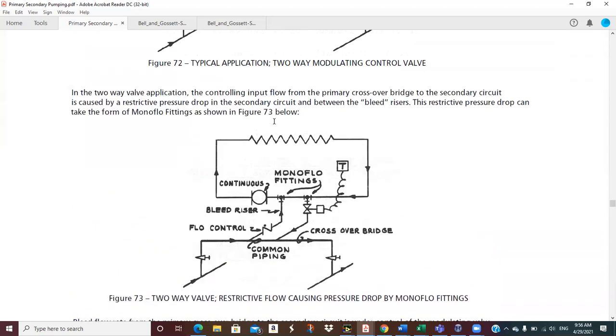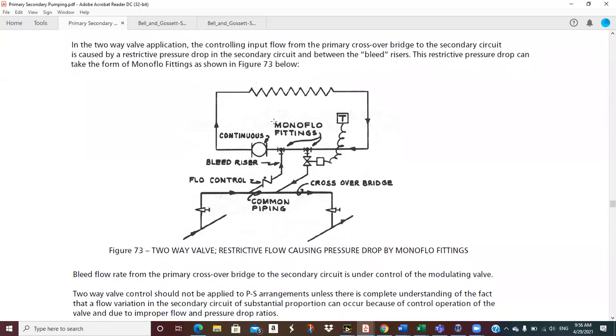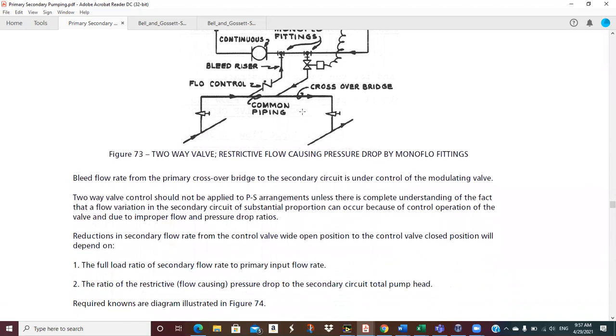Okay, that's a mouthful. But what that's saying is if you don't get the flow ratios and the pressure ratios that we're going to define in a minute right, when this valve goes from open to shut, you will drastically affect the flow rate in the secondary. And that is not your intent. Our intent is to have a constant flow rate in that secondary. But if you screw this up, when this thing goes from open to shut, you may change the flow rate up here by 75 or 80%, which is going to make it darn difficult to keep those people comfortable in that secondary. So again, danger, danger, danger if you don't read this and understand it. And so that's what we're going to do.